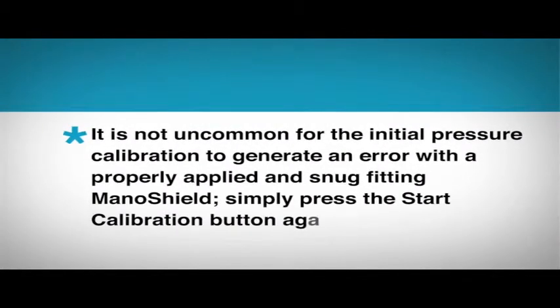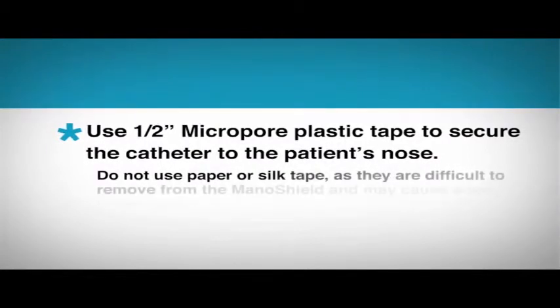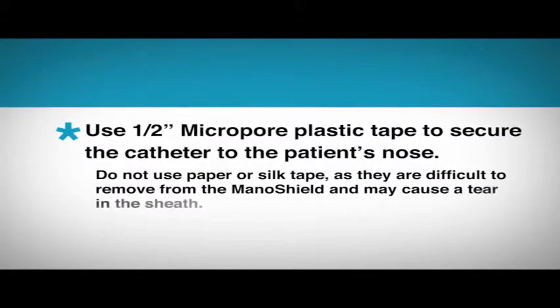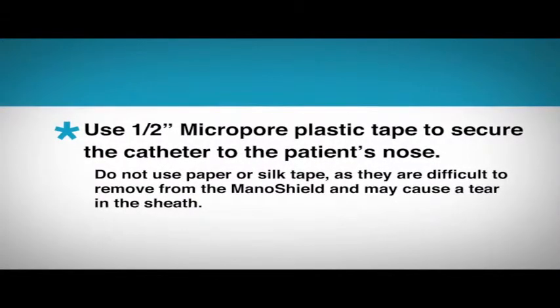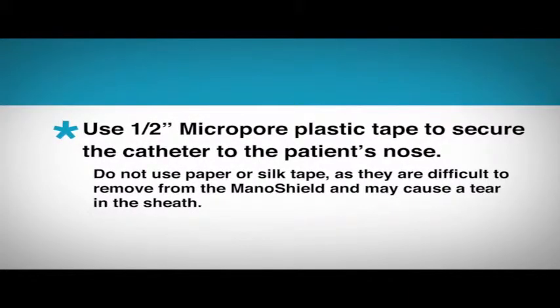Simply press the Start Calibration button again. Use half-inch micropore plastic tape to secure the catheter to the patient's nose. Do not use paper or silk tape, as they are difficult to remove from the Manoshield and may cause a tear in the sheath. After the procedure, removal of the Manoshield.